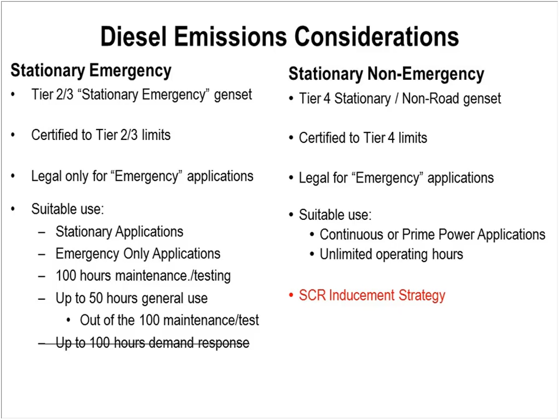The inducement strategy is basically a reflection of EPA's concern that emissions control devices should work in a consistent and effective manner and should be maintained in good working order. So the inducement is designed to do just this. It's to induce the operator to keep the thing working. It's designed into all selective catalytic reduction systems that are used on large Tier 4 stationary generator engines. It is basically a system that will detect a fault in the emissions reduction system and provide visual warning or notification to the operator for a fault. The inducement part of it is that if the fault goes unresolved, the engine will derate or shut down unless action is taken. Now, there is a warning period before that shutdown or that derate occurs.